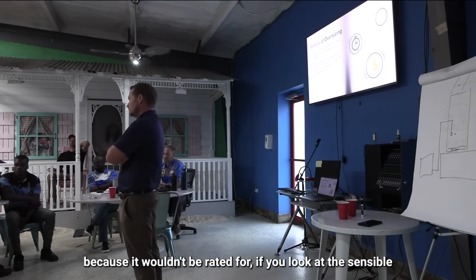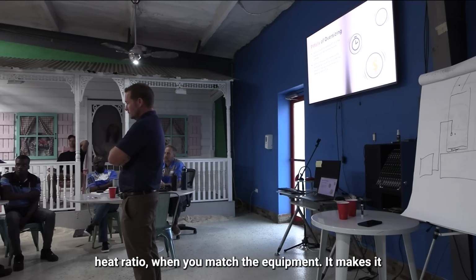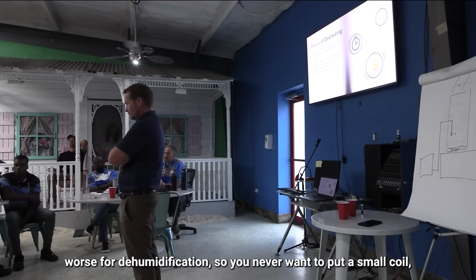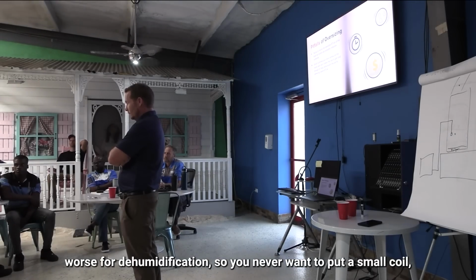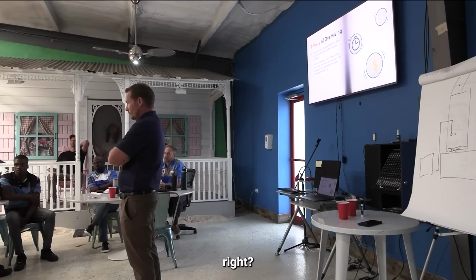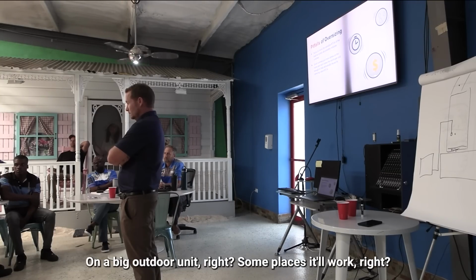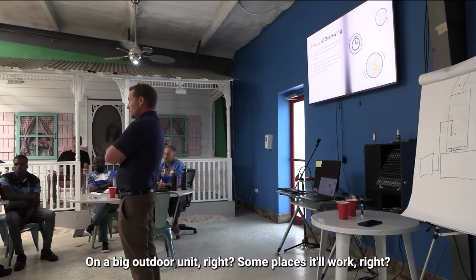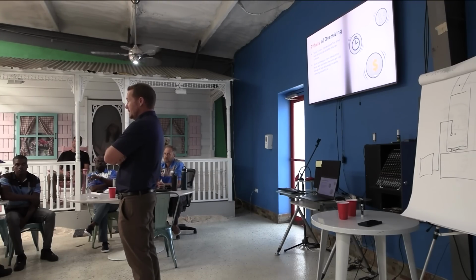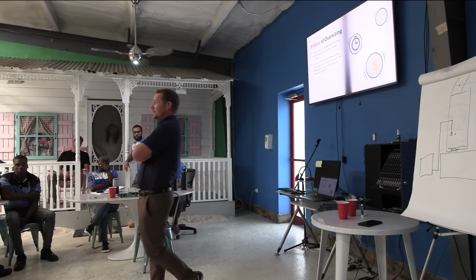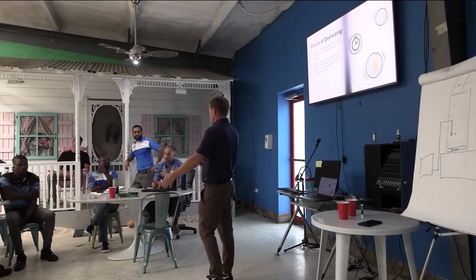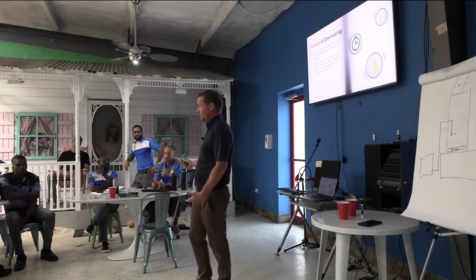If you look at the sensible heat ratio when you mismatch the equipment, it makes it worse for dehumidification. So you never want to put a small coil with a big outdoor unit - in some places it'll work, but it's not ideal. Coil size is a big deal. So when you think about it, remember how we talked about filters - bigger filters are better, right? Like what Matt was showing.